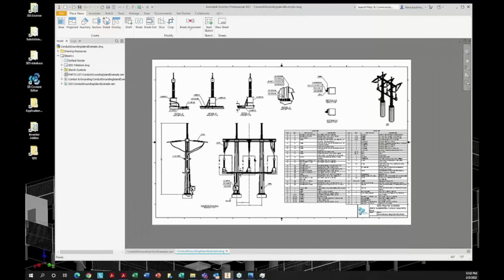If you look at the model here too, we did this large assembly, island subassembly, and to do it detailed like this is a lot easier than that old method of detailing the entire bay and trying to put 400 balloons in an entire bay and identifying things. This makes it so much easier to have dedicated drawings for the islands, so that at construction, the constructors can look at your elevation view, and you identify the island in the elevation view. That's all you need to do, other than the interconnecting cables. But you identify the island.